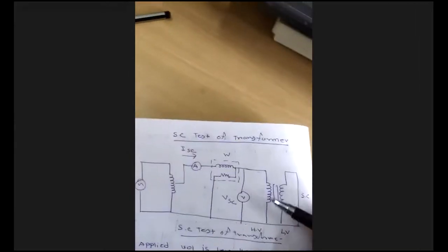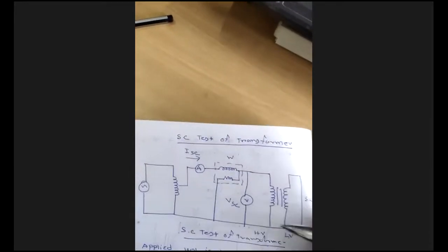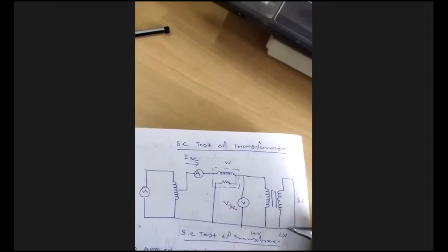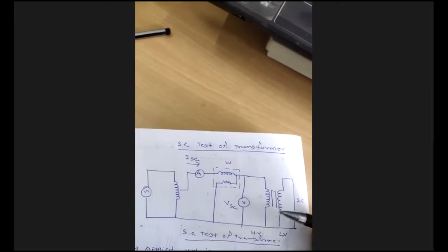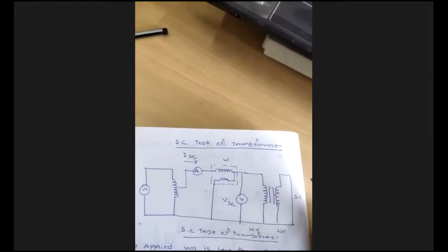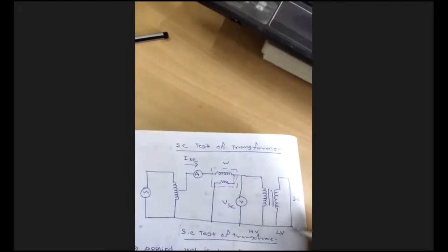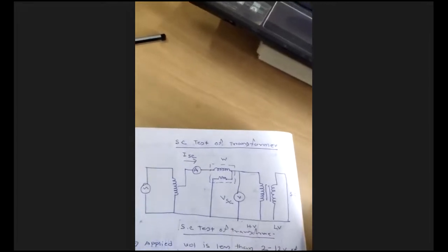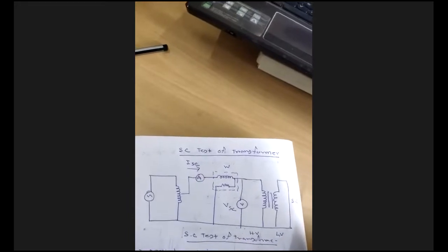And also applied voltage is less. Here are some points we have to remember in the short circuit test, and that is applied voltage is 2 to 12% of the rated voltage। जो applied voltage है 2 to 12% of the rated voltage ये हम लोग को अप्लाई करना होगा। ठीक है, second point, core loss is very small, here core loss is very small, and it has only the I square R losses, here we only have the I square R losses. These 3 points we must remember in the short circuit test of the transformer.